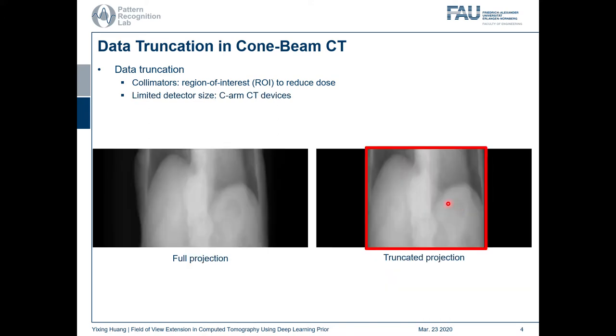In the other scenario, because of the limited size of flat panel detectors, the projections of large objects might be outside of the detector, especially for human abdomen or thorax. For example, this is one projection image in a wide enough detector where we can see the complete projection in the horizontal direction. However, in practice, because of the limited size of the detector, only the projection inside a red box is acquired, and the projection is truncated again in the horizontal direction.